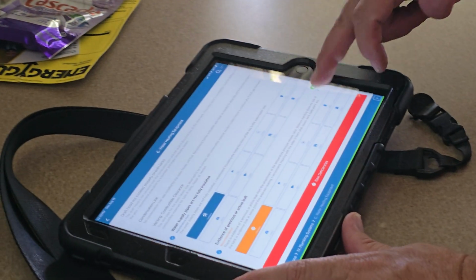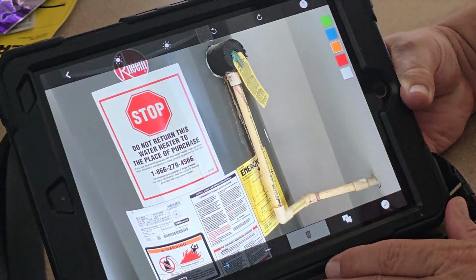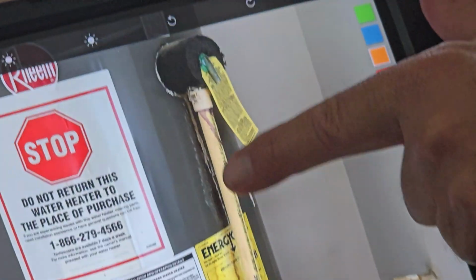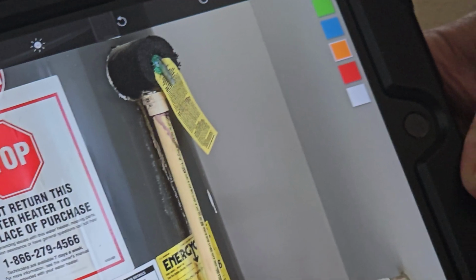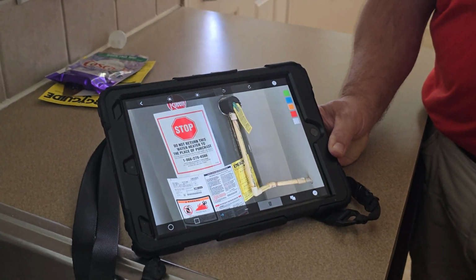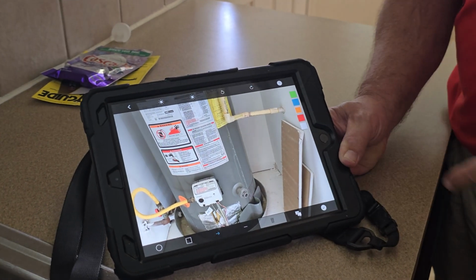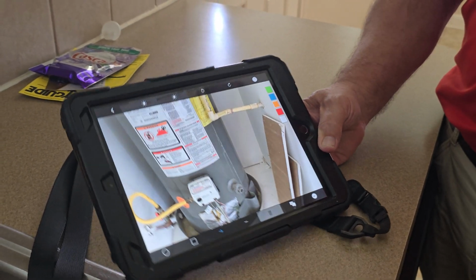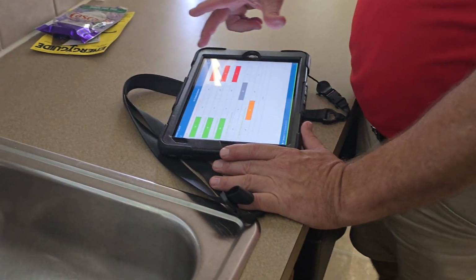So I would ask the sellers about that. Right here next to the valve. Does it look like it was leaking now? Well, I can see mineral staining, moisture staining down the water heater tank here. I don't see moisture on it presently, but it could have dried. That could be something that happens when it's in use. With this staining, I would just recommend asking them about that. If no repairs have been made, I would recommend that a plumber come take a look at it. If repairs have been made, they can probably provide documentation for that.